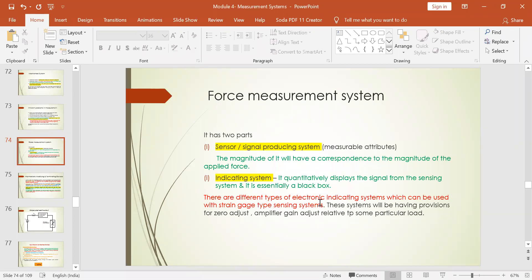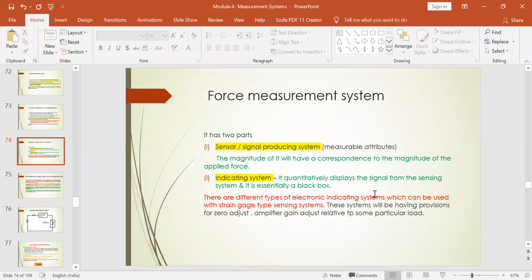In order to work, you should be using a strain gauge type of sensing system which senses the applied force, and that applied force will be displayed using the electronic indicating system — the black box. These systems will have provisions to zero adjust and amplify, i.e., gain adjust, based on the particular load applied. There are three stages: the detector stage where the sensor plays a vital role, the indicating system as the intermediate stage which amplifies and displays the received input signal.